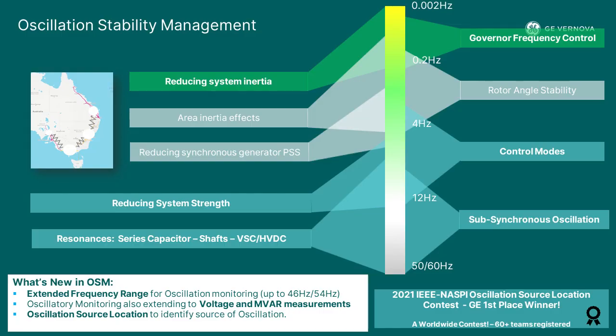What we've also added to our portfolio is what's called oscillation source location, because we know that while oscillations on the grid can propagate, identifying the location that's adding or causing the oscillation is important. It may not be the same location where you're seeing a large oscillation. Being able to pinpoint where energy is being introduced and oscillations are being caused is something that we've added to our oscillatory stability management.